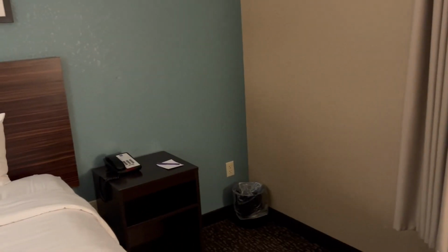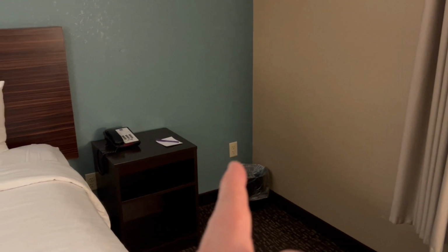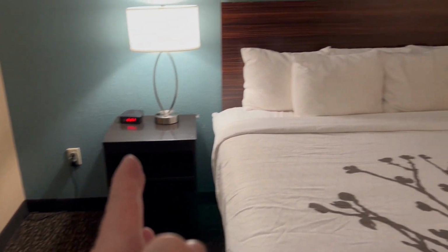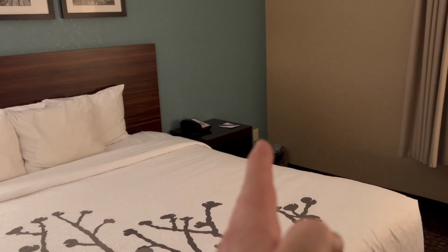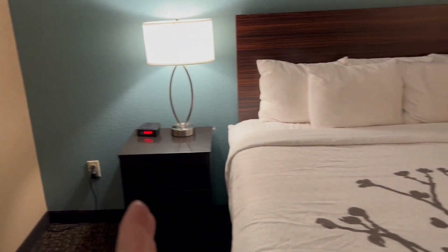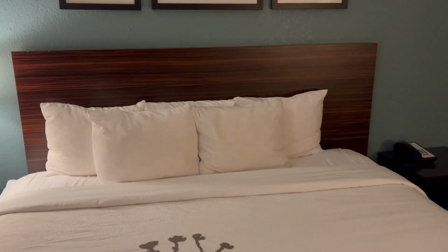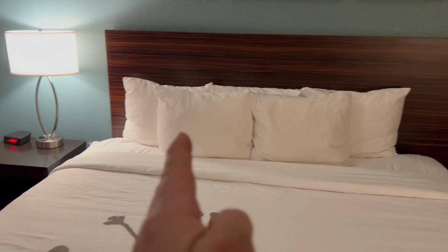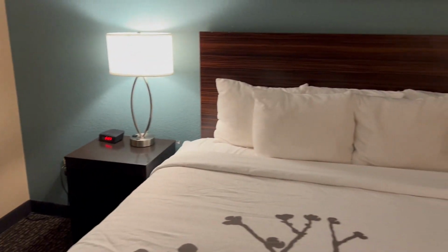Now I've got something called the 6 foot, 12-foot rule. And what is that? If I go from this receptacle along this wall to this receptacle, I did measure it before, it's about 12 feet between those receptacles, and that's okay. So let's say the bed wasn't here, and let's say we have a lamp over here with a 6-foot cord. I should be able to take that lamp and plug it into that receptacle over there, and without moving the lamp, I should be able to plug it into that other receptacle over there.